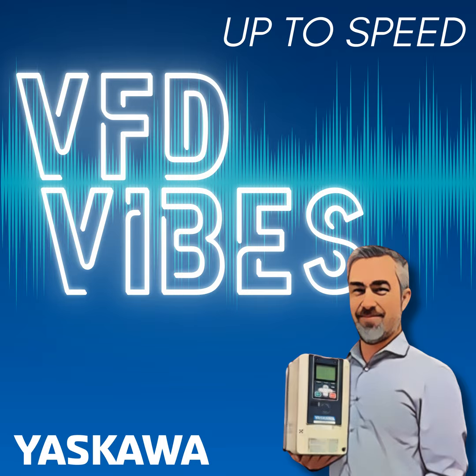Well, a loop antenna is designed to pick up the magnetic portion. An electromagnetic field has two components, the electrical component and the magnetic component. And the loop antenna is designed to pick up the magnetic component, whereas a wire antenna, just a piece of wire up in the air, is designed to pick up the electrical component. And most of the components of noise in any kind of industrial facility are definitely magnetic. They're caused by currents flowing through wires. Because you might have 480 volts of voltage, but you might have thousands of amps of current.